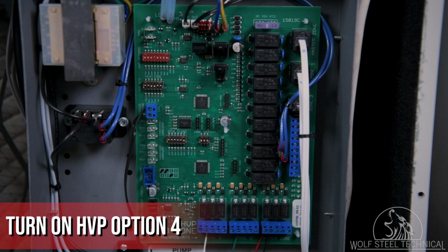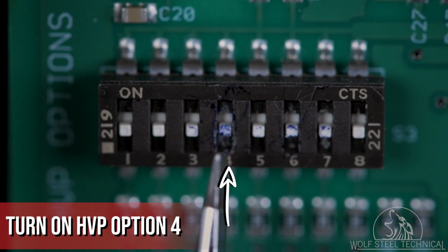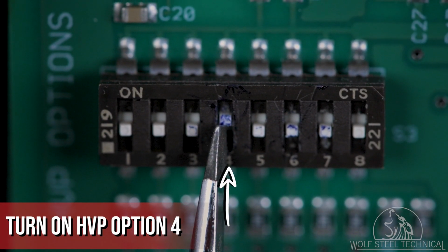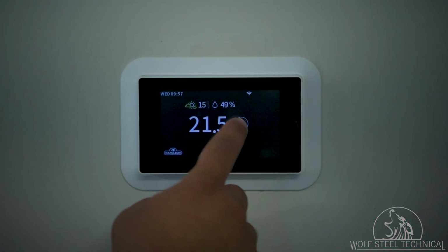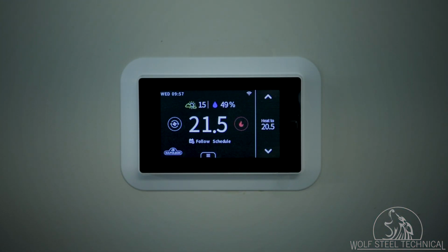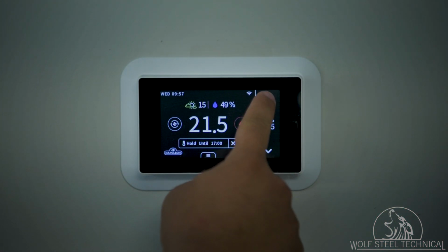Now focus on the HVP option switches and set the HVP option 4 switch to the on position. This will enable CPT. The calibration is now complete, and the thermostats can be operated as desired for both heating and cooling.